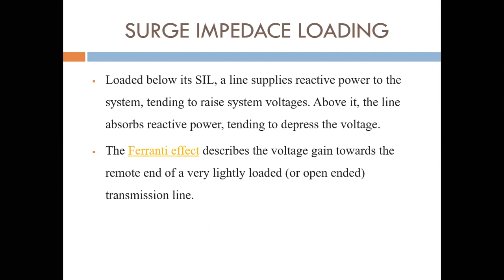Therefore, the surge impedance loading is also called the power transmitted. That means PR is equal to VRL squared by Z naught, where VRL is the receiving end voltage and Z naught is the surge impedance. PR is called the surge impedance loading of the line. This is a common method for increasing the power limits of a heavily loaded line, but there is a limit beyond which it is neither economical nor practicable to increase the value of VR.